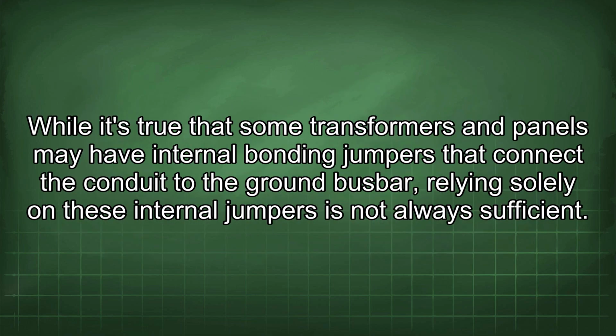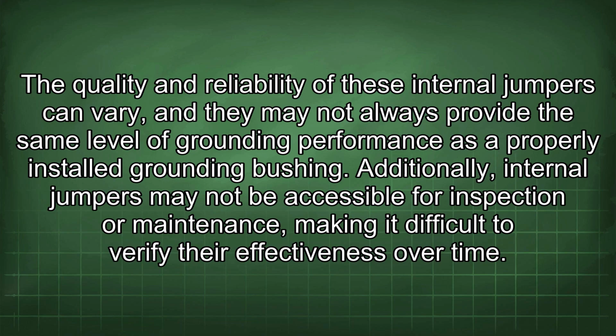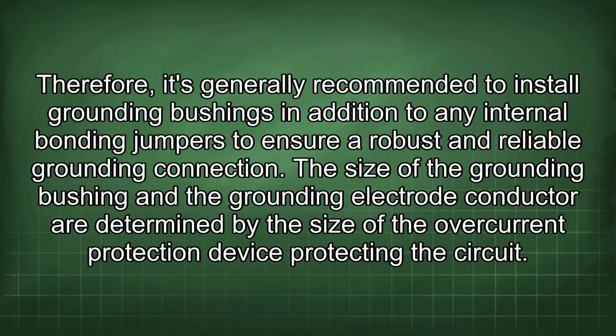While it's true that some transformers and panels may have internal bonding jumpers that connect the conduit to the ground busbar, relying solely on these internal jumpers is not always sufficient. The quality and reliability of these internal jumpers can vary, and they may not always provide the same level of grounding performance as a properly installed grounding bushing. Additionally, internal jumpers may not be accessible for inspection or maintenance, making it difficult to verify their effectiveness over time.